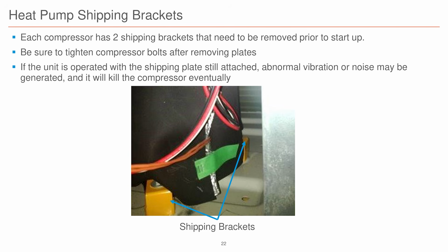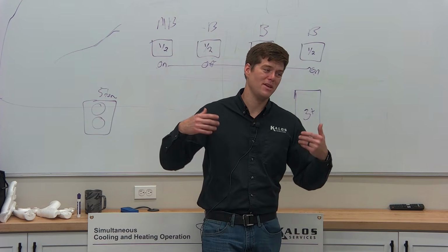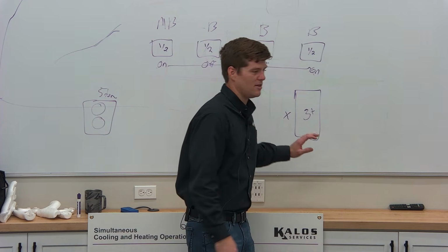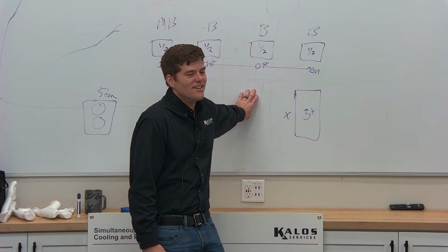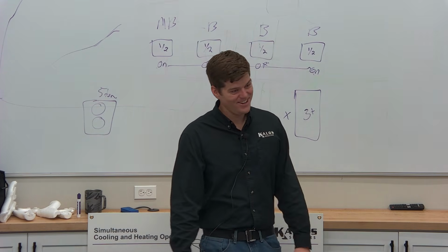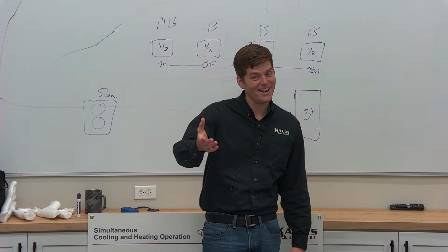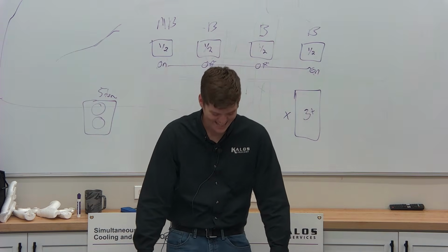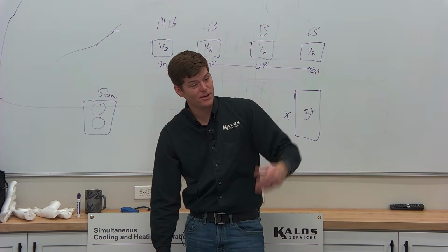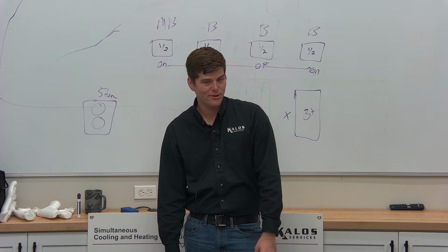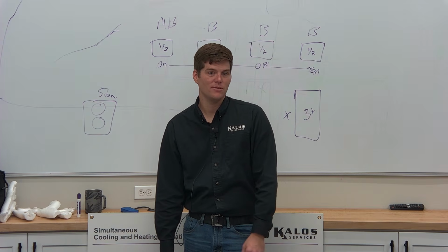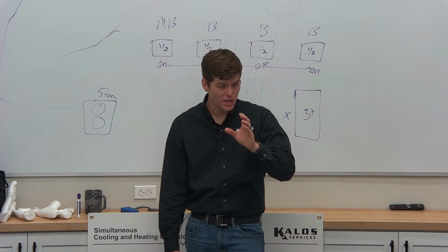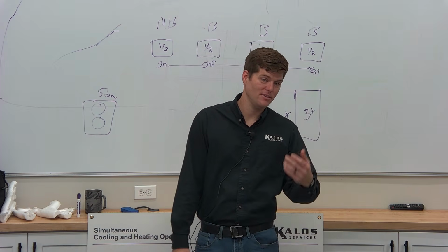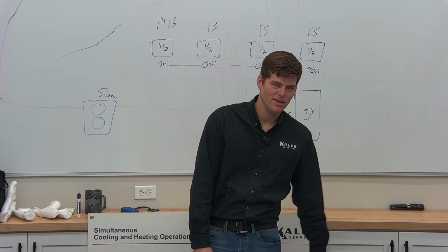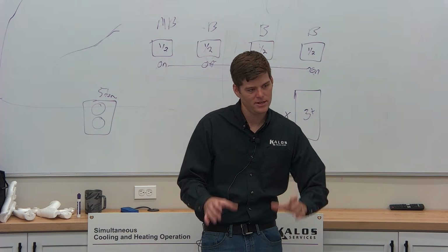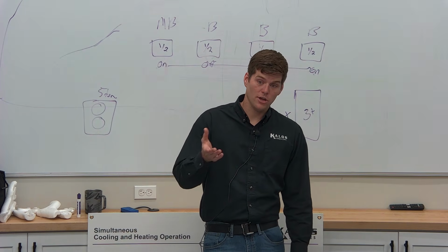If you go to a VRF system and it's got a failed compressor, or the compressor is making a awful racket, or you put your hand on the unit, everybody's done it, and you're like, ugh, look under the compressor. You might find a shipping bracket underneath it. If I had a nickel for every time I found a dead compressor that had been shaken to death over a year, some make it a couple months, some make it 2 years, where these are still underneath there. They make them yellow, but the blankets cover them perfectly. So if you're the one installing a unit, just check it.